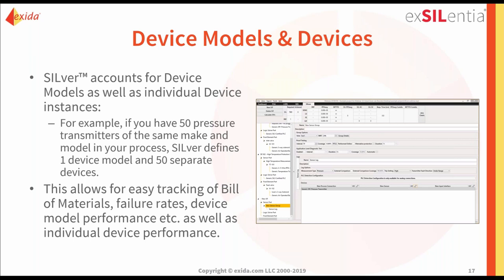Device models are a representation of a particular make and model of a transmitter. Once specified within your project, it's made available for all future selections from an easy drop-down list, so you can simply pick from your project-preferred vendors. You may have one device model but 50 separate devices, and the tool keeps track of all of them. Eventually, in operational and maintenance phases, you can add serial numbers. By linking all devices to a particular device model, you can easily determine failure rates and look at overall device performance.